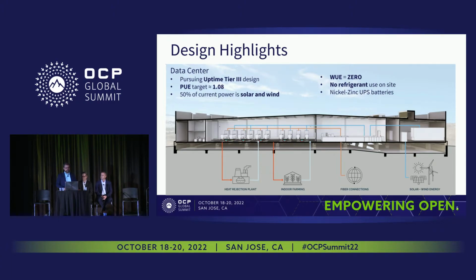As Trenton mentioned, we are targeting an uptime tier 3 redundancy profile, so we are concurrently maintainable all the way to the rack level. You'll see that through the mechanical, electrical, and all supporting services throughout the design. He also touched on we're targeting a PUE of 1.08, and that's largely attributed to the fan savings you'd see in a traditional data center, and the fact that we have no compressors whatsoever in this facility.